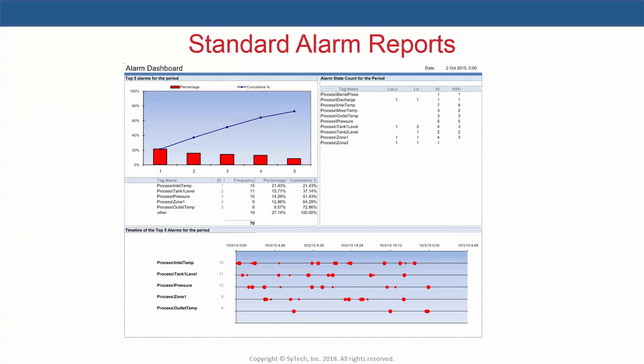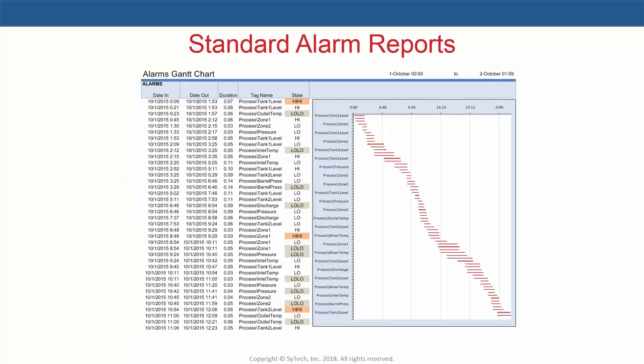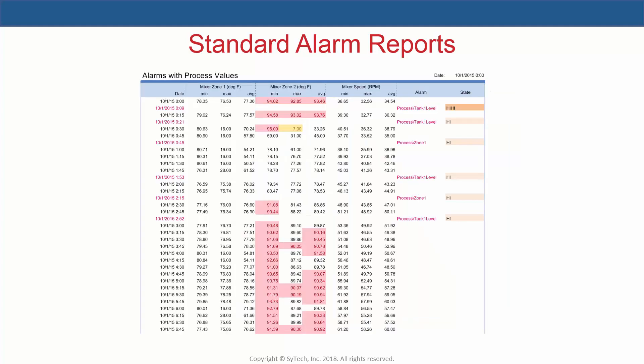Examples of standard alarm reports include an alarm dashboard which collects alarm history over the day and displays results as a Pareto chart, useful for visualizing the most frequently occurring alarms. Another report visualizes alarm history as a Gantt chart, displaying the timeline and duration of alarms, useful for identifying sequences and patterns. A third example combines alarms and process history into a single inline log to correlate process variables with alarms.